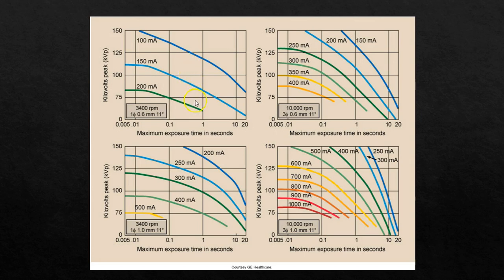So that's kind of how the whole thing works. Looking at this other rating chart, this tube has an anode that can spin at 10,000 RPM, it's got a one millimeter large focal spot, and this is for three-phase. With a three-phase generator, large focal spot, and high-speed anode, at 100 kVp and 300 mA, I can go all the way out to probably about five seconds — a ridiculously long exposure time. That just goes to show how much more power this tube can stand compared to the first one.